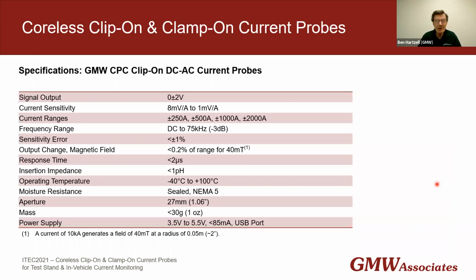So just a quick review of the specifications. The output on this one is analog, 0 ± 2 volts. The current ranges 250 amps to 2000 amps. Frequency range DC to 75 kilohertz. The error and sensitivity about 1%. One important thing is the output signal change in a magnetic field is quite low, 0.2% for a 40 millitesla field. And 40 millitesla is what you get from 10 kiloamps at about a distance of 50 millimeters. So this will tolerate a high current quite close to the sensor. Response time is 2 microseconds. The insertion impedance is very low, less than a picohenry.